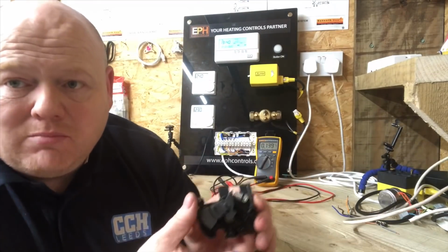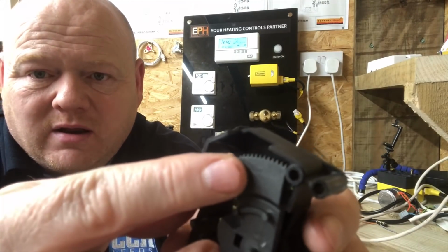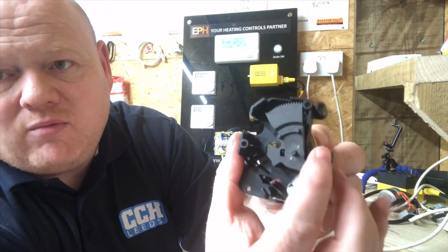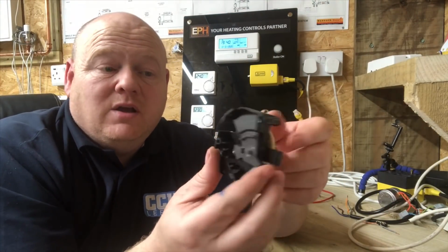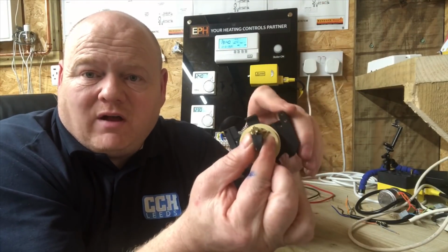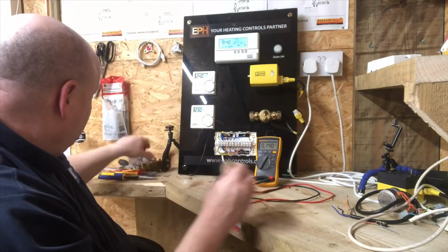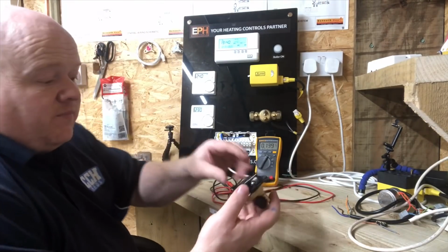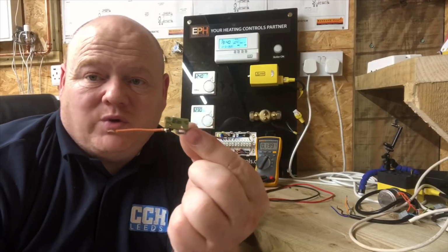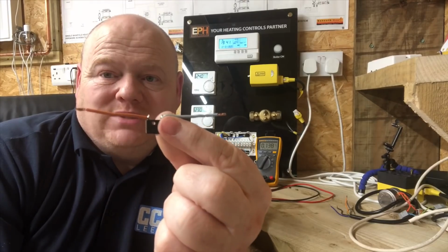When that motor moves, it moves them cogs in there, and that moves that round, and as that moves that round, it does a couple of things. One, it moves a little paddle in there, and that opens and closes the valve for the direction of the water inside the valve. And the other thing it does is we have a micro switch, and now this is where your orange wire and your grey wire come into play.